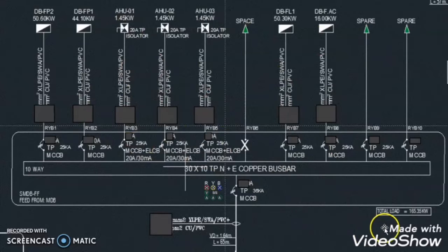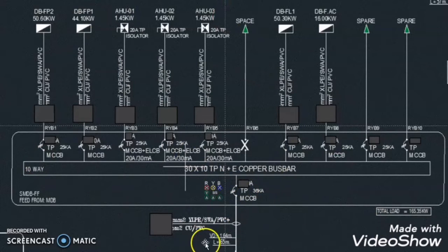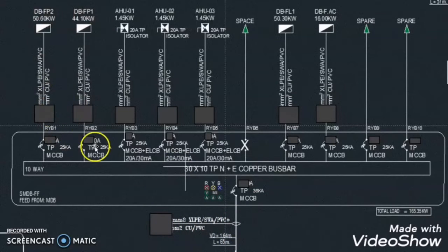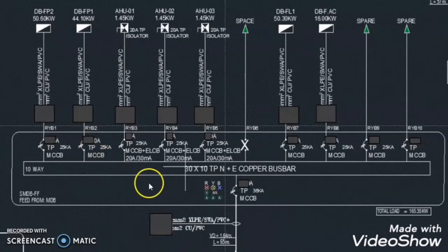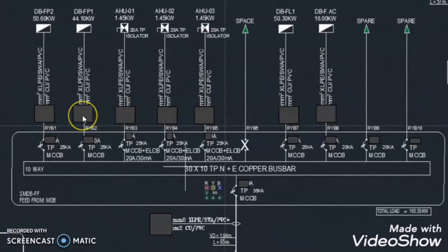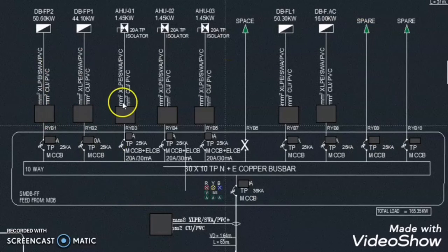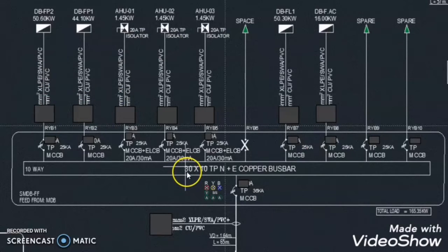This is the SLD for one SMDB and we will find the incoming breaker rating for this SMDB, the incoming cable size of this SMDB, and we will calculate the breaker rating for all outgoing loads and the size of the cables for all outgoing loads connected with this SMDB. All calculations for the breaker rating and cable rating will be as per the DEWA standard. I will make another video to design one SMDB as per ADDC regulation, but in this video I am designing this SMDB as per the DEWA standard.